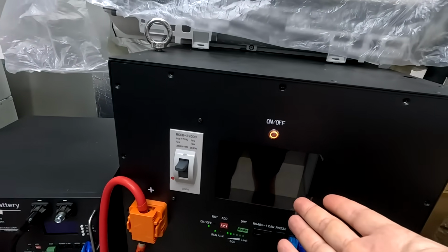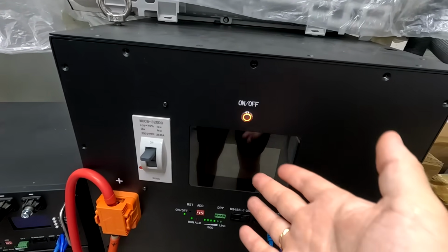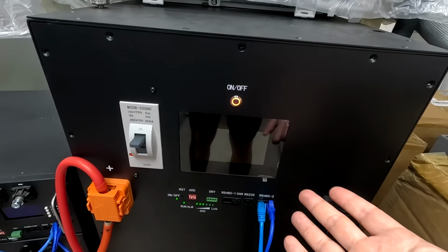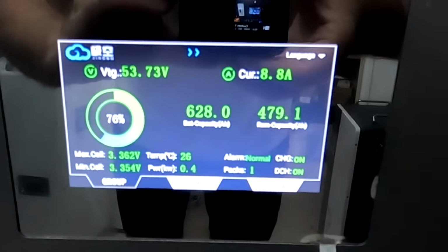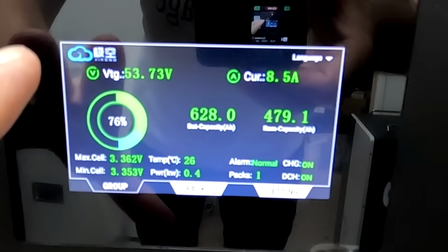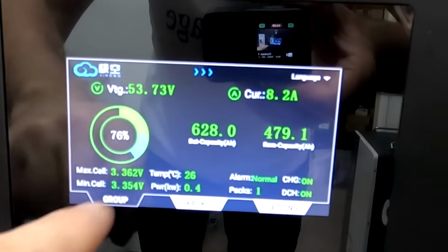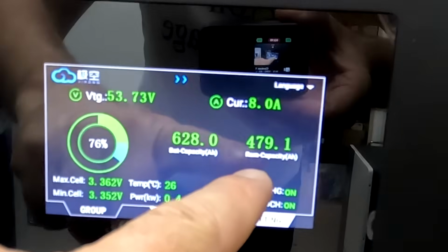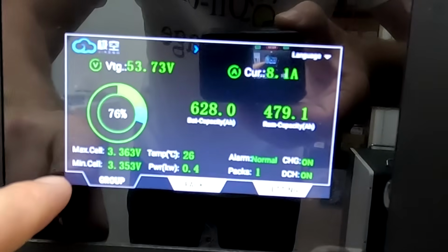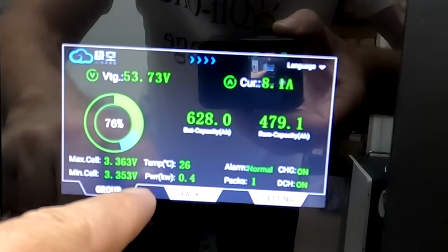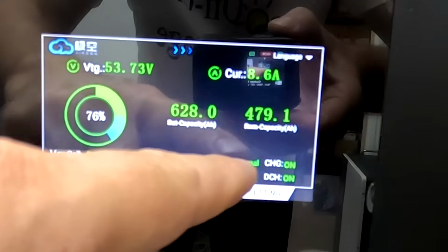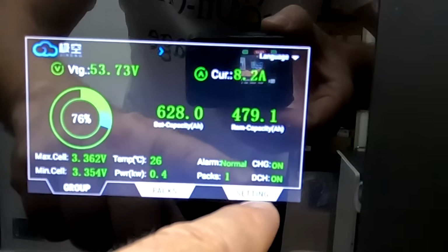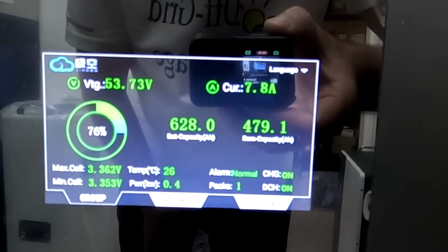Okay, so at the moment with version 19.13 or anything below version 19.21, you get the main screen here with the voltage of this battery, the current for this battery, capacity for this battery, remaining capacity, min-max cell voltage, temperature, the power, if there's any alarm, and if the charge and discharge MOSFETs are on or off.